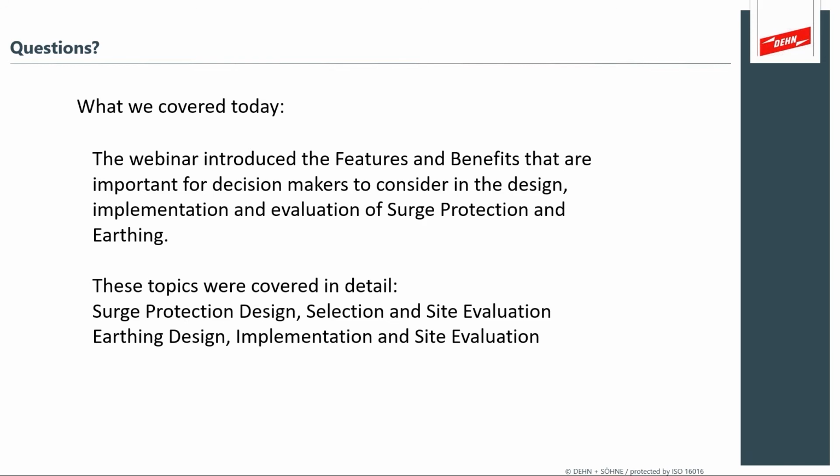And what you will often find is that you have to apply both a lightning protection system and internal surge protection devices to prevent the risk of fire. And so it's part of a thorough risk evaluation process. DEHN has proprietary software that we've developed that's available, and we could certainly take this offline and go into much greater detail. This is a great topic.